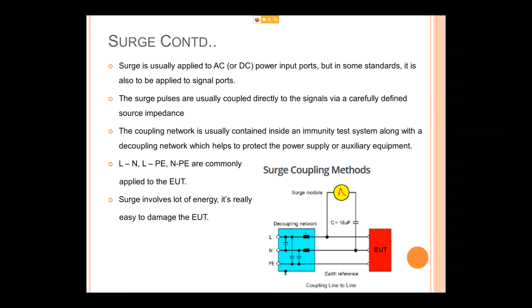So there will be a CDN, and the CDN will include a decoupling network. That will have 3 lines, that's nothing but line, neutral and ground. We will be sending the signals in different ways, either line to neutral, line to ground, or neutral to ground, applied to the EUT. If the EUT withstands all the surge pulses which we give on the power cord or the signal port, then your system has passed. The surge involves lots of energy, so it could easily damage your system or easily make it die.